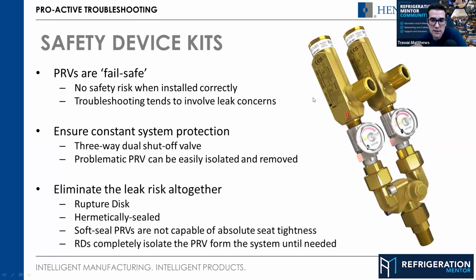Quick question, it means you've still got system protection as well. That's the important point. You could do the same thing with a single isolation valve, but then your system's unprotected. So something happens, you have to run away for something, you forget to unlock the valve again, and, God forbid, something happens to the system, it's going to be a bad one. So this means you're always protected.